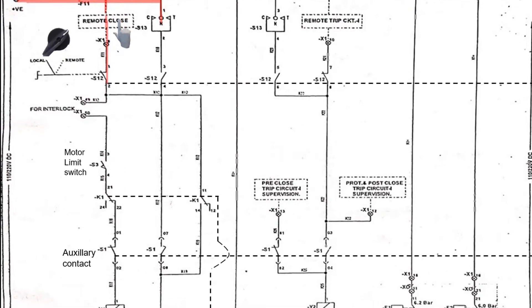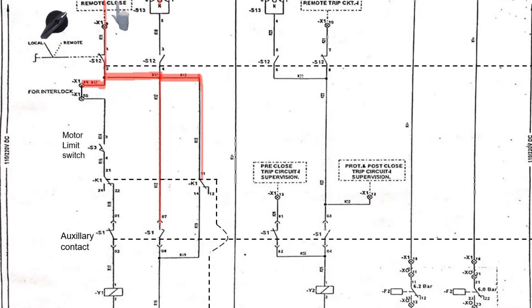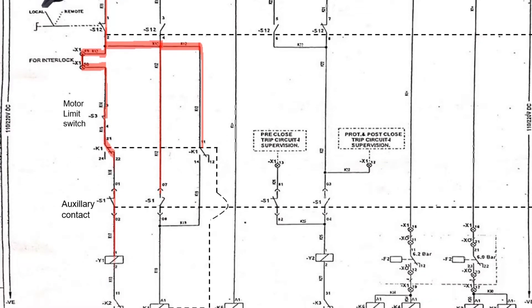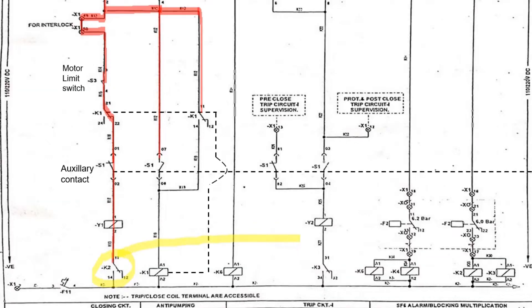Then the current will flow in this direction. Current will not flow for the right-hand side paths but will flow from the left side if the interlock is in OK condition. The current will stop if the spring is not charged, and if the spring is charged, the motor limit switch will be in closed position and the current will flow downwards. It will flow through auxiliary contacts S1 and closing coil Y1, but will stop at K2, which is an SF6 gas supervision relay.